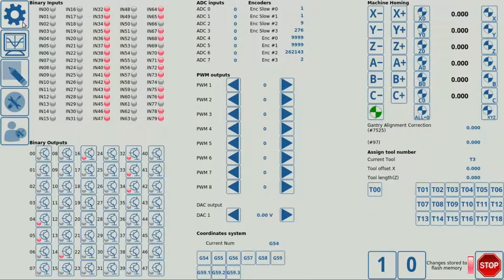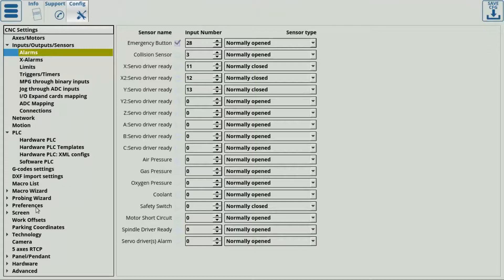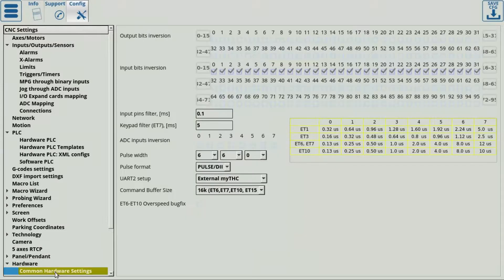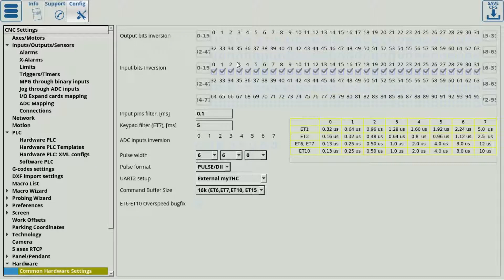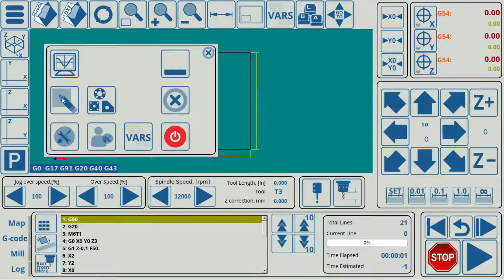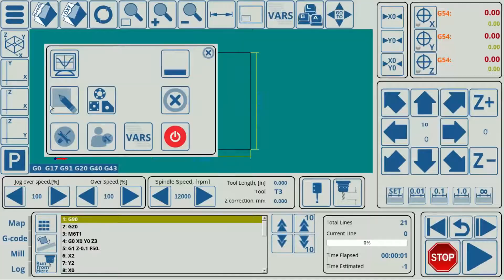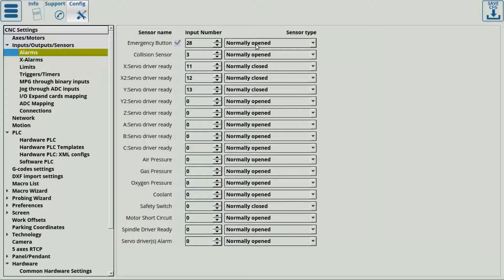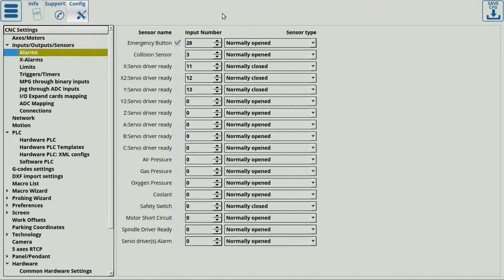The reason you would like to specify it is because you can also edit this standard behavior through your common hardware settings, where you can flip the default state of that input or output to be on or off by default. However, in my case, this input number 28 is typically off, so in my alarms I set it to be normally opened.